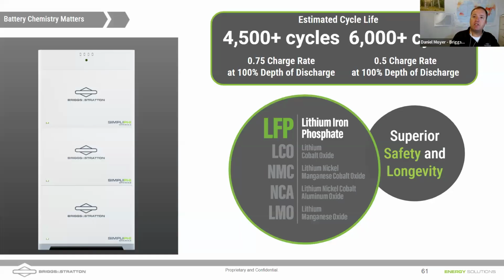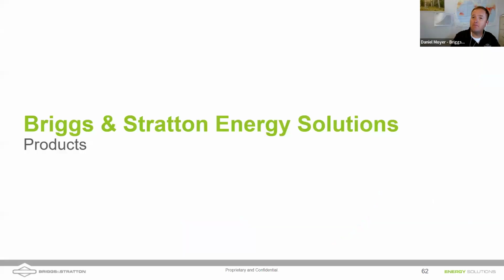Even at 100% depth of discharge, we're still offering 6,000 cycles at the C/2 discharge rate. At C/1.3333, we can still offer 4,500 cycles - that's like 16 years or 12 years. So notice here, I'm not changing the depth of discharge, I'm changing the rate at which I'm cycling, the C rate, which actually dictates cycle life more so than depth of discharge.